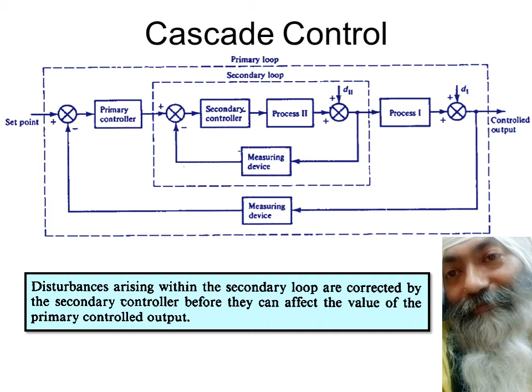This is the basic block diagram of a cascade control, highlighting that the disturbances acting within the secondary loop are corrected by the secondary controller before, as you can read here, they can affect the value of the primary controlled output. So that's how D2 is taken care of by the slave and D1 is taken care of by the master. The task is divided, so things become faster. As such, this is called cascade control.